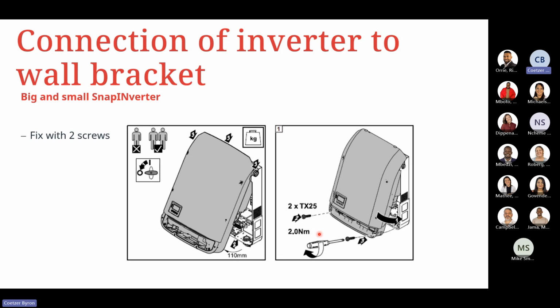Again, we emphasize heavily to make sure that the two screws on the far left and the far right-hand side are fastened tightly. What we've noticed is some clients will avoid tightening correctly and they just leave it. What happens is you'll develop arcs on either the AC side or DC side, and this will greatly affect the unit and also the RMA side. So we recommend making sure that it is installed correctly on site.